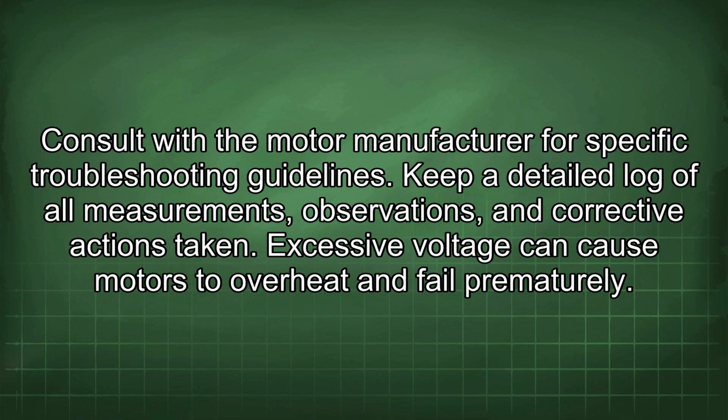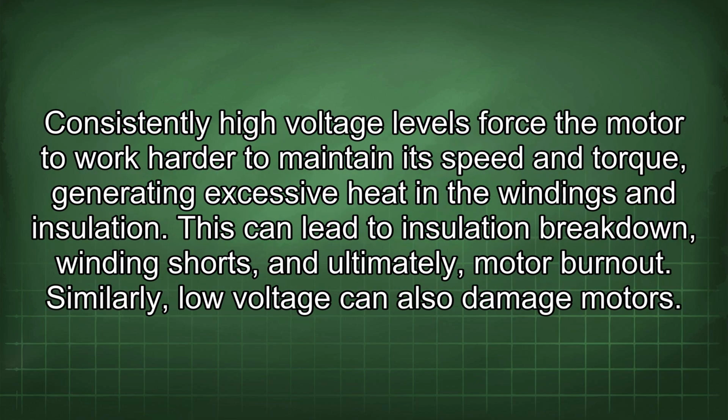Excessive voltage can cause motors to overheat and fail prematurely. Consistently high voltage levels force the motor to work harder to maintain its speed and torque, generating excessive heat in the windings and insulation. This can lead to insulation breakdown, winding shorts, and ultimately, motor burnout.